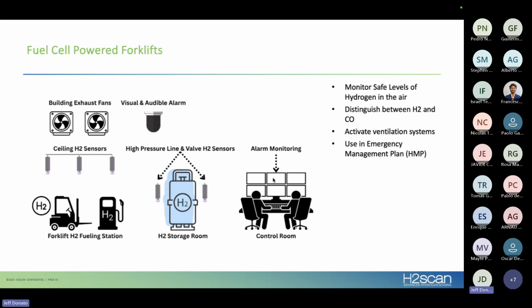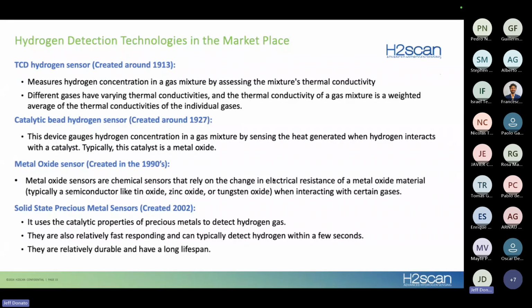So for example, we had an auto manufacturer who was measuring for carbon monoxide. Their carbon monoxide alarms kept going off, but they were using forklifts with hydrogen fueling stations. And what they were measuring in their carbon monoxide sensors was not carbon monoxide, it was hydrogen, and it was confirmed that way. So be aware that when we go through the sensors here in a moment, you're going to notice that a lot of sensors have cross sensitivities. And so that's something that has to be taken into account based on the system.